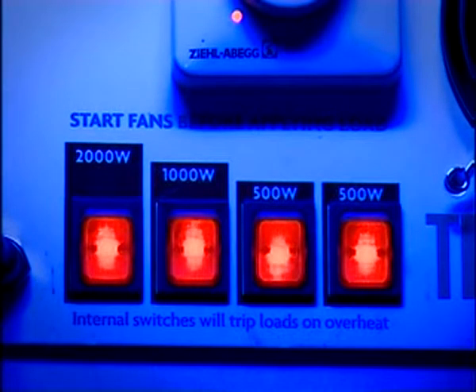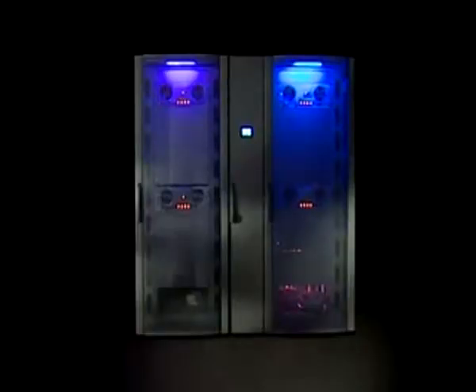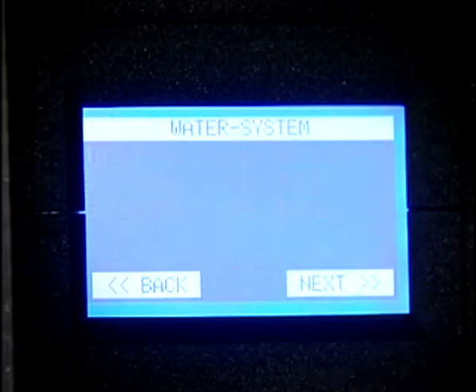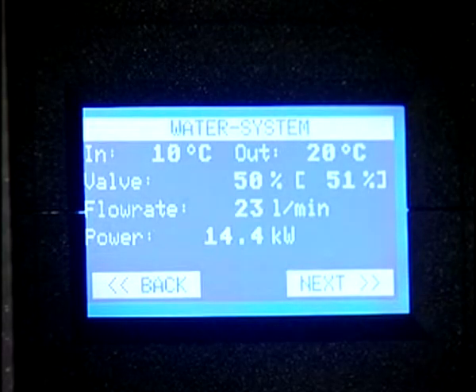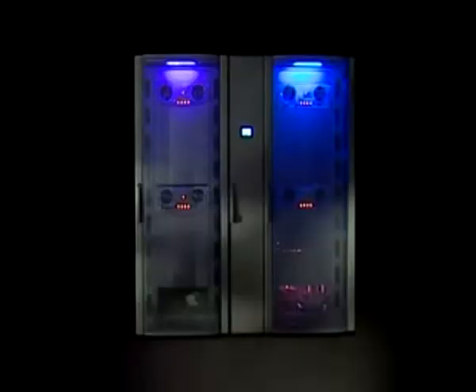As can be seen in this demonstration, heat loads have been placed in the enclosure to mimic high-power blade servers. The heat load has been taken up to 20 kilowatts, and you can see the inlet and the outlet temperatures are stable. Cool air is passed across the front of the enclosure.